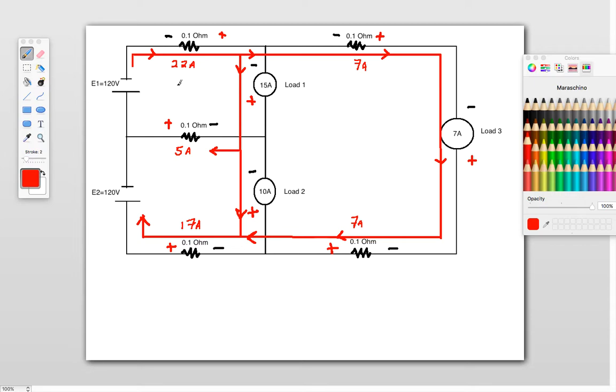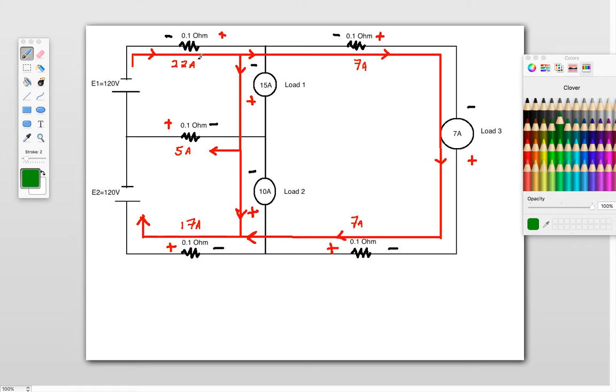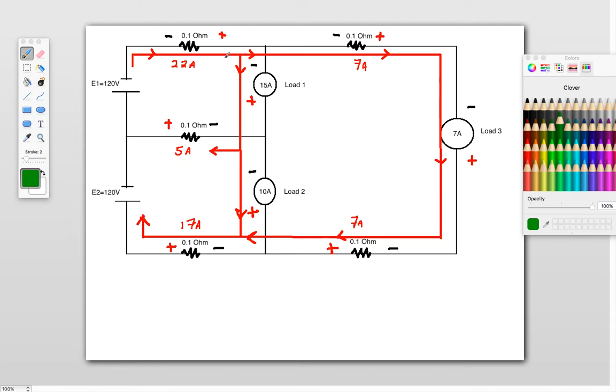So now what we want to do is determine where voltage drops are across these. This resistance, it's not really a resistor. I draw them in so we can show our polarities, so it makes it easier for doing our voltage drops, but really what we're talking about is I-squared-R losses. And really what that is, we're talking about the amount of resistance within the wire itself, creating a voltage drop before it gets to the load. So the loads are going to have a smaller voltage applied to it as a result of the voltage drops across the wires that are feeding it.